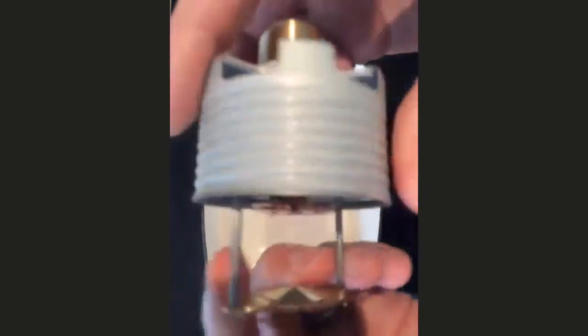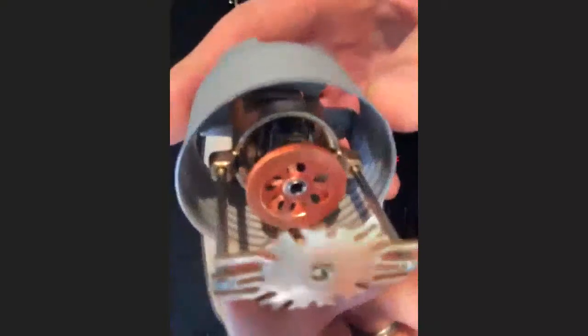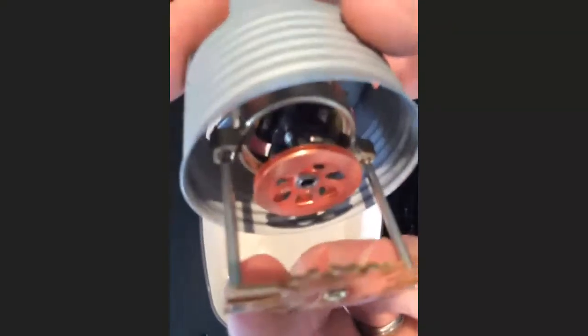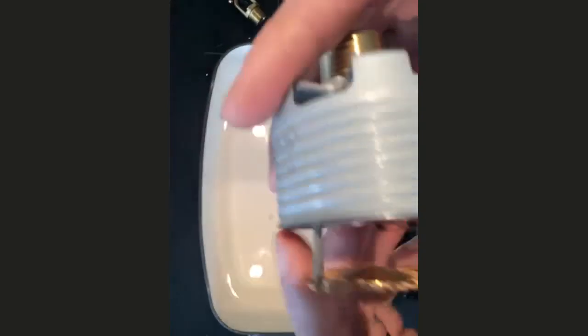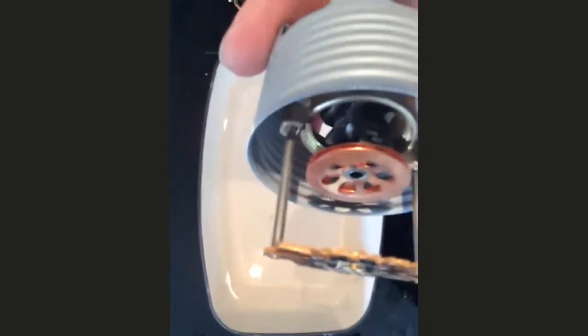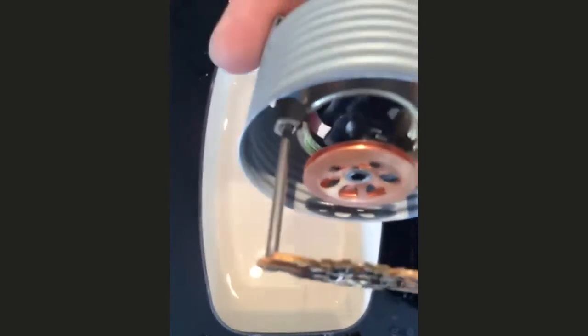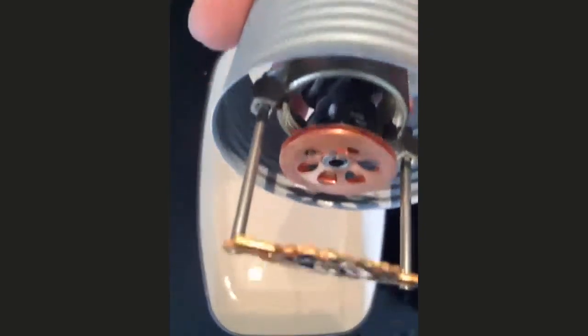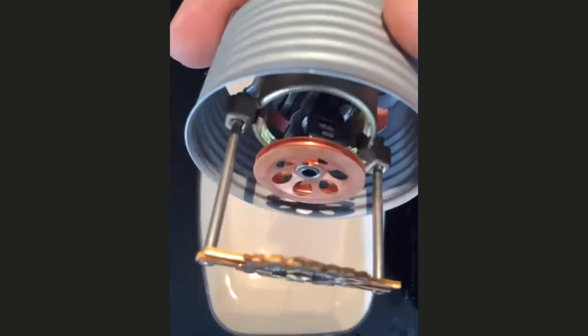So I just had a question, where would you use a 93 degrees head? Yeah, I mean, obviously not very often. Somewhere where the ambient temperature is going to be a lot higher. So it might be some sort of industrial processing place where the ambient temperature may be higher. Remember, they're set to operate at 30 degrees above ambient. So 63 degrees is kind of the highest normal point that we would be expecting.